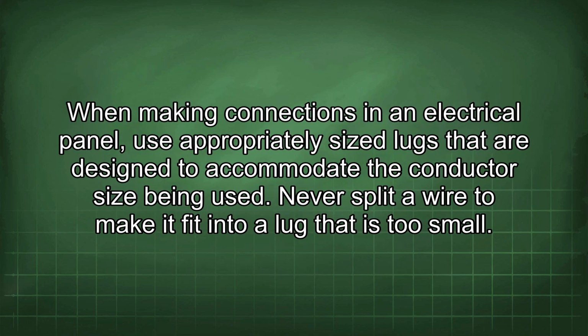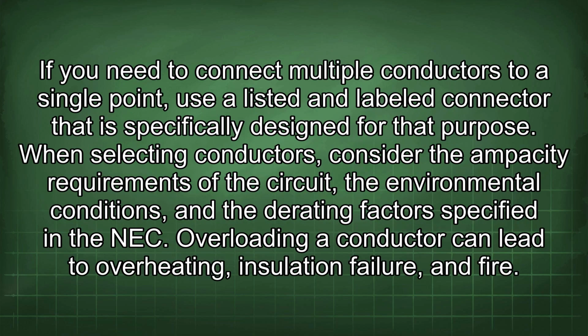When making connections in an electrical panel, use appropriately sized lugs that are designed to accommodate the conductor size being used. Never split a wire to make it fit into a lug that is too small. If you need to connect multiple conductors to a single point, use a listed and labeled connector that is specifically designed for that purpose. When selecting conductors, consider the ampacity requirements of the circuit, the environmental conditions, and the derating factors specified in the NEC.